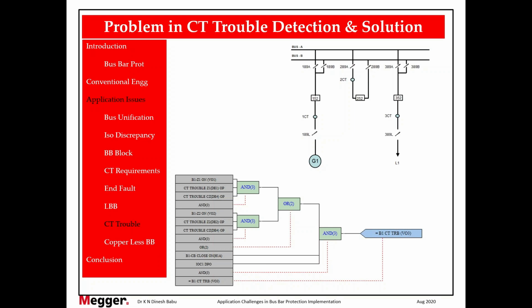Bay 1 in zone 1, is the CT trouble in zone 1, is the CT trouble in check zone. If all three are satisfied, okay, it comes out. So this is for bus A.